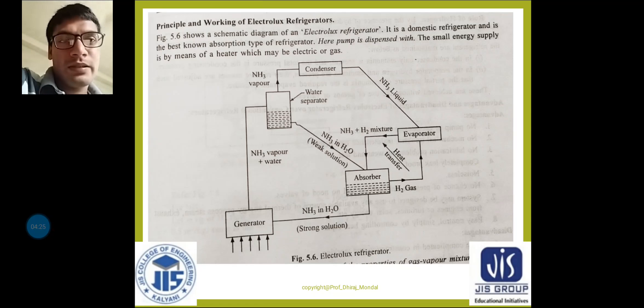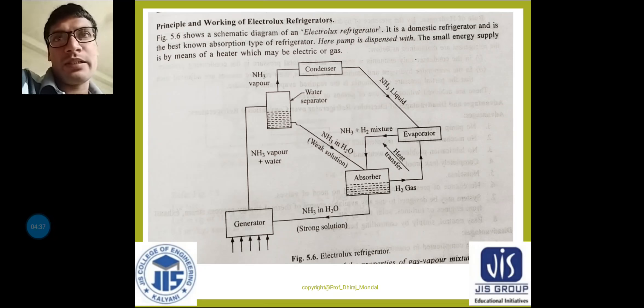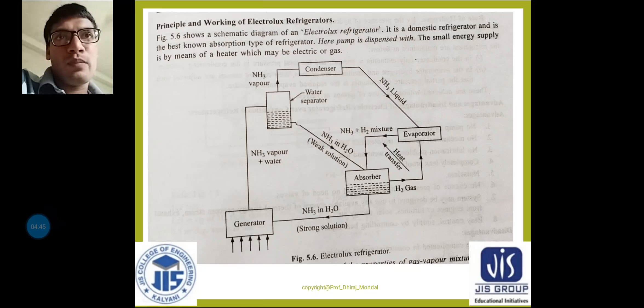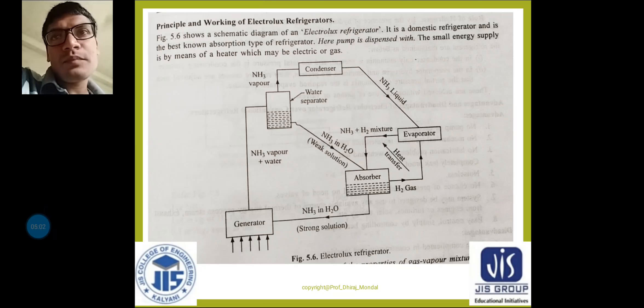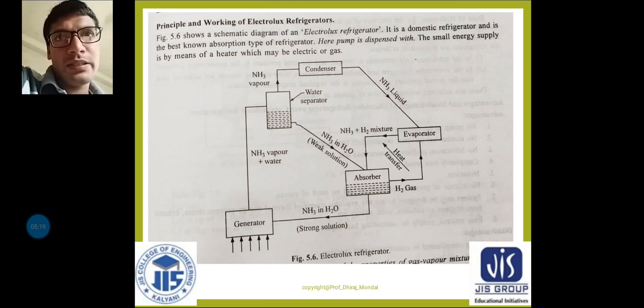The ammonia (NH3) is used as the refrigerant — this is important for MCQ questions: in the domestic Electrolux refrigerator, ammonia is the refrigerant, not the absorbent. Ammonia is used because it possesses most of the desirable properties of a refrigerant. Though it is toxic and not otherwise preferred in domestic appliances, it is very safe in this system due to the absence of any moving part, giving the least chance of leakage.